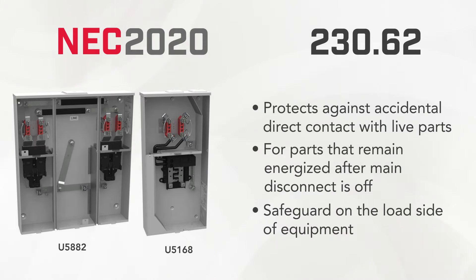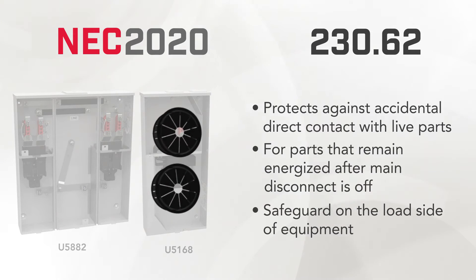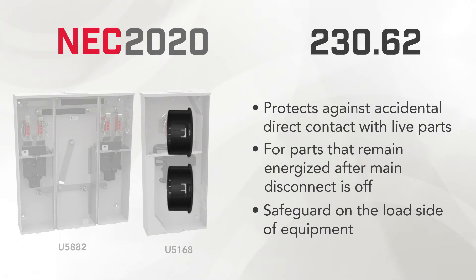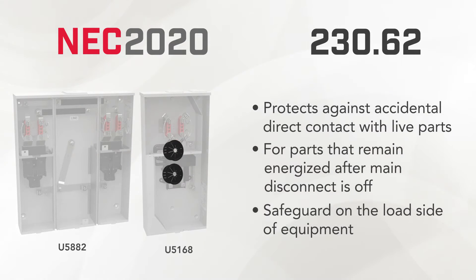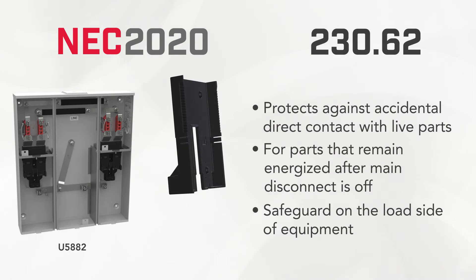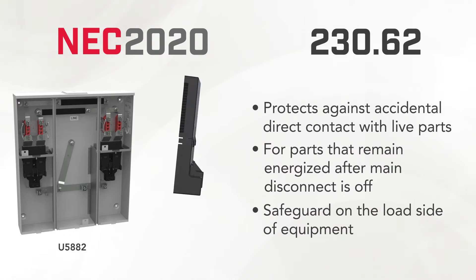This is a safeguard for personnel working on the load side of service equipment. Milbank has utilized different solutions to accomplish this depending on the product. For example, the bushing insert used on the main breaker set screws in the U5168 protects against contact with energized parts. Other products such as the U5882 through U5886 multi-position meter mains utilize bus covers to protect against contact with the energized bus.